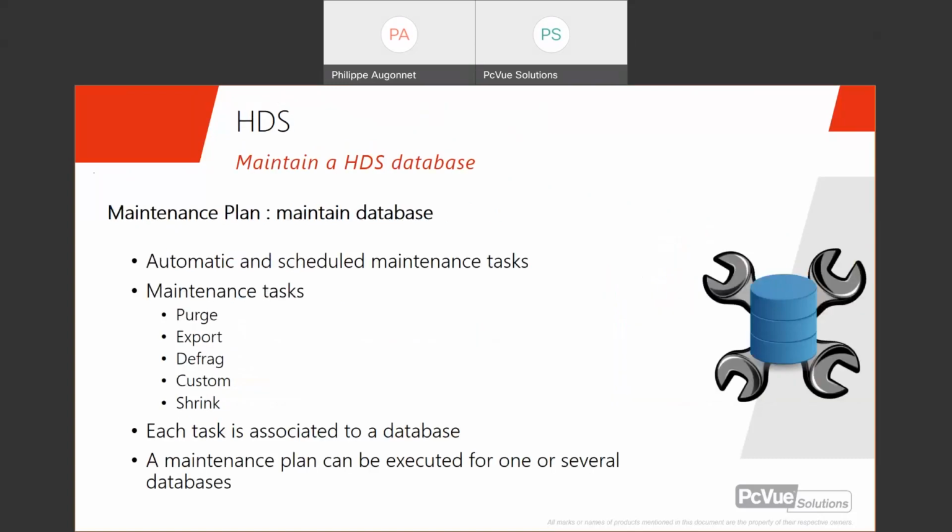One of the tasks you can perform within PcVue for your SQL Server database is a maintenance plan. You can do automatic maintenance tasks or scheduled maintenance tasks depending on your need. It includes purge, export, defrag, or shrink, for example. It's kind of usual tasks for a maintenance plan. And each task is associated to a specific database. And then you can execute the maintenance plan either for one or several databases.